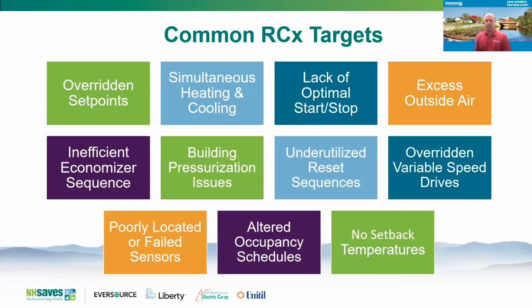Overridden VFDs, see those all the time. No temperature setbacks, poorly located or failed sensors. Really important to understand that the sensors and equipment are working properly. One of my mantras is don't trust the graphics. Just because it shows you a supply air temperature of X, don't believe it. Go measure, go verify, because oftentimes the sensors are wrong. I've seen sensors miswired.